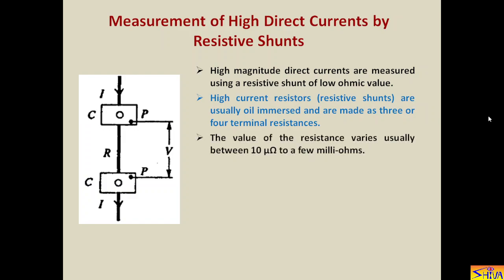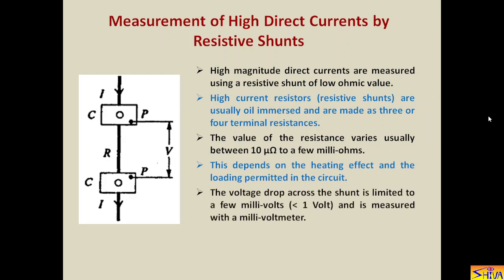The value of the resistance varies usually between 10 micro ohms to a few milli ohms. Because current is very high, we want to limit the heat generated, that is power dissipated. The voltage drop across the shunt is limited to a few millivolts, less than one volt, and it is measured with a millivolt meter. The P terminals are voltage terminals and a millivolt meter is connected between P and P.